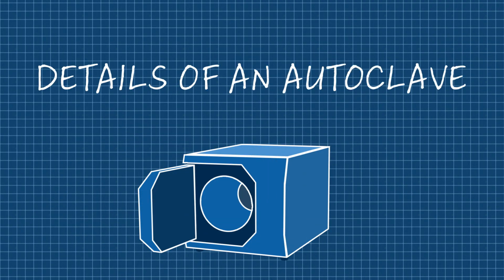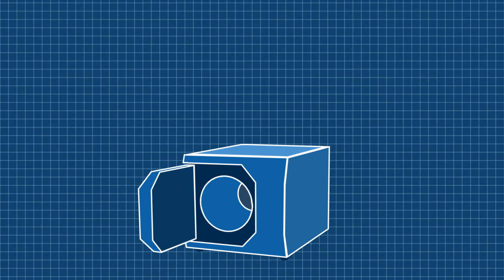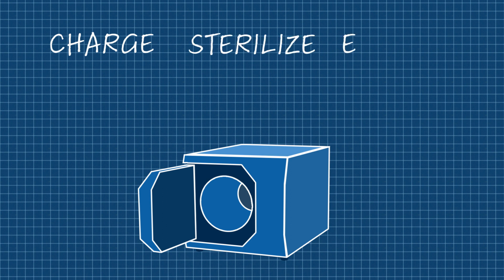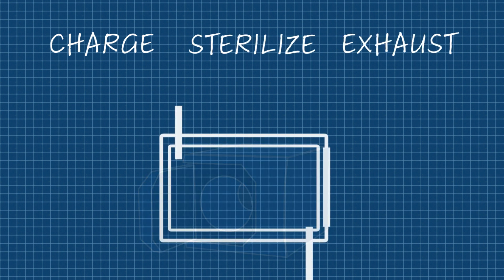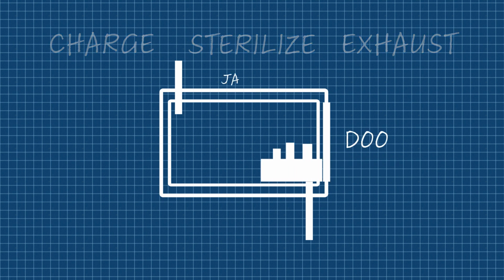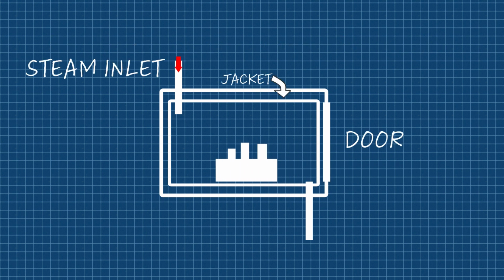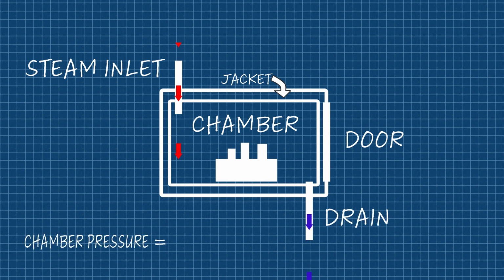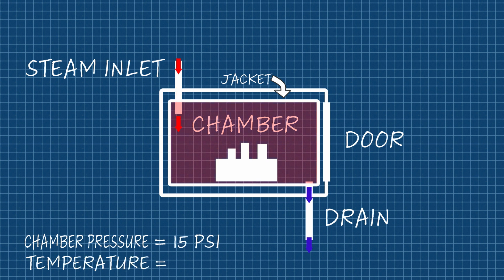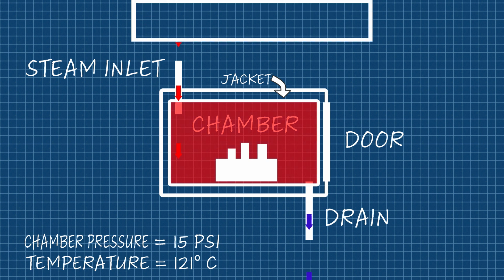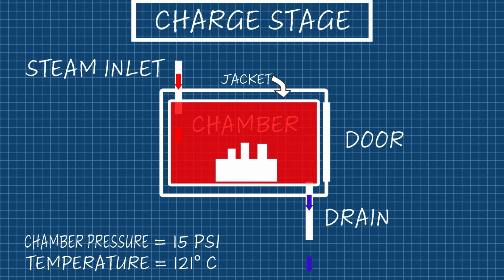Let's break down the stages of the autoclave cycle into more detail. An autoclave cycle consists of 3 stages: charge, sterilize, and exhaust. After the autoclave door is sealed, steam enters through the steam inlet valve and pushes air from the chamber out through the drain. As this occurs, you will see the chamber pressure increase. The temperature will increase to 121 degrees Celsius or 250 degrees Fahrenheit. This is called the charge stage.